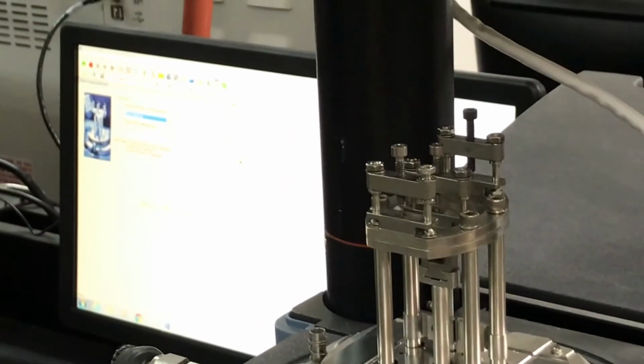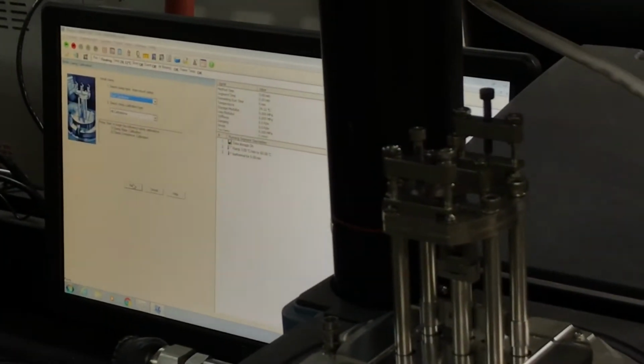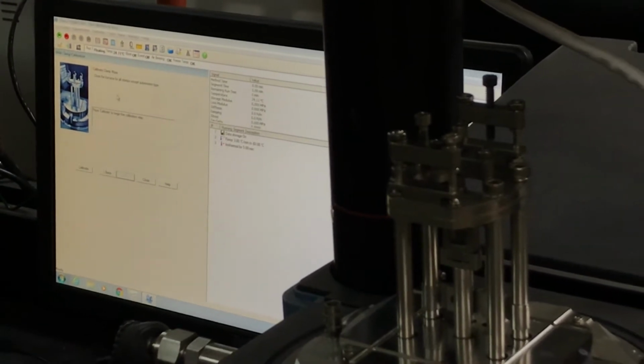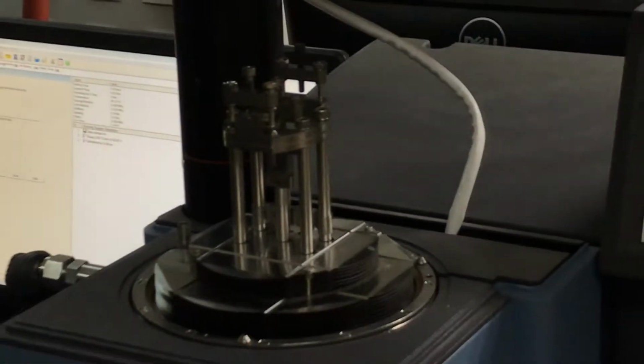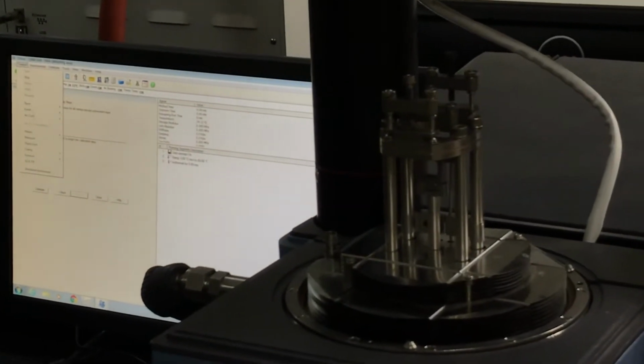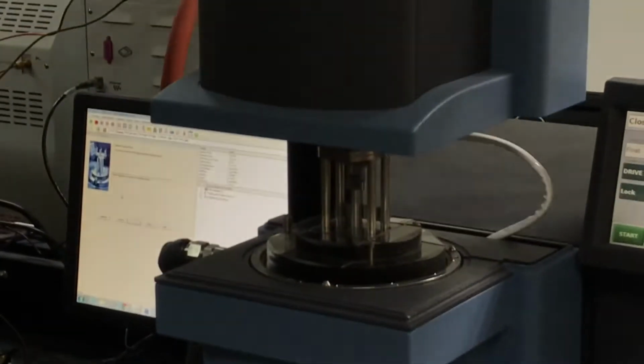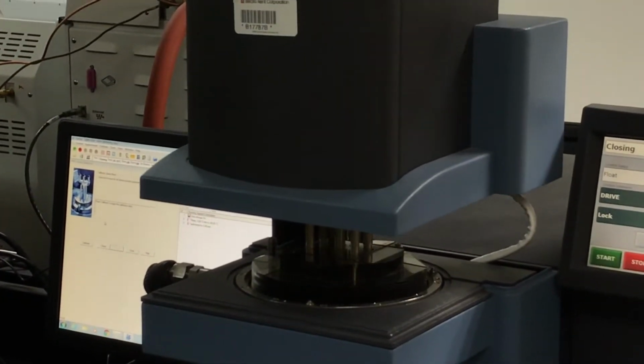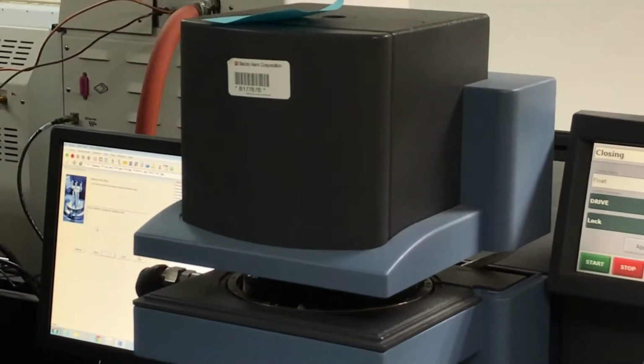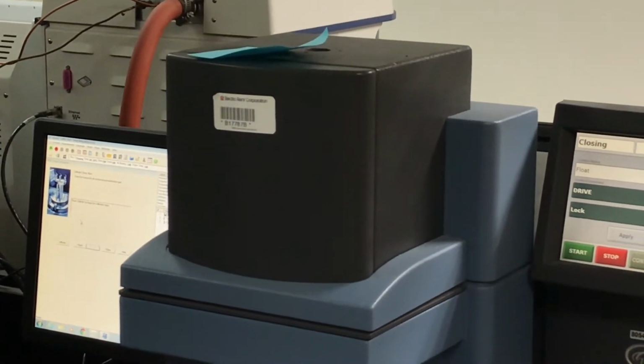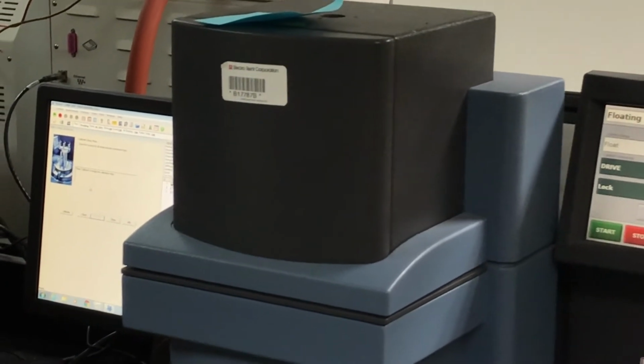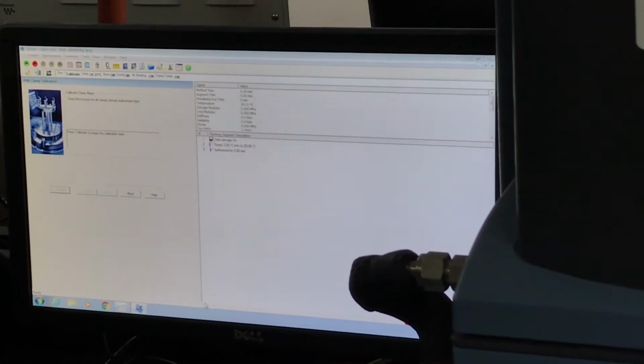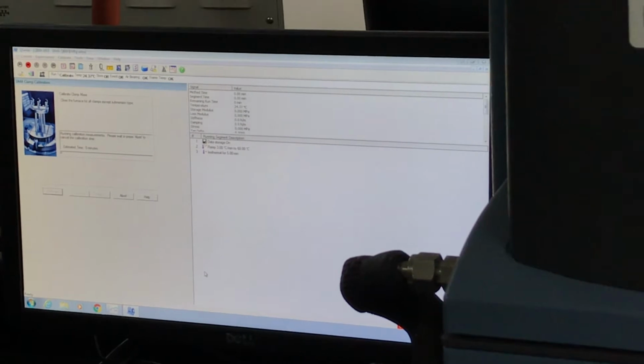So press next to begin the following clamp calibrations. So next, let's see, close the furnace. We can go ahead and go to this control tab, and then go to furnace and hit close. So now that the furnace is closed, we can go ahead and start the calibration. This could take a couple minutes.